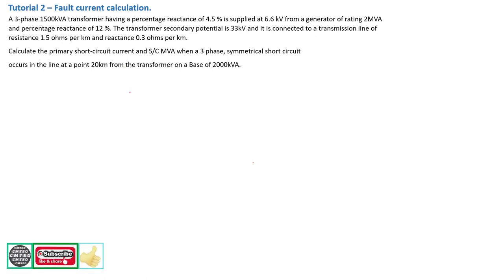This is tutorial 2. The problem statement says: a three-phase 1,500 kVA — that's 1.5 MVA — transformer having a percentage reactance of 4.5% is supplied by a 6.6 kV generator rated at 2 MVA with a percentage reactance of 12%. The transformer's secondary potential is 33 kV, making it a step-up transformer — stepping up from the generator for transmission.